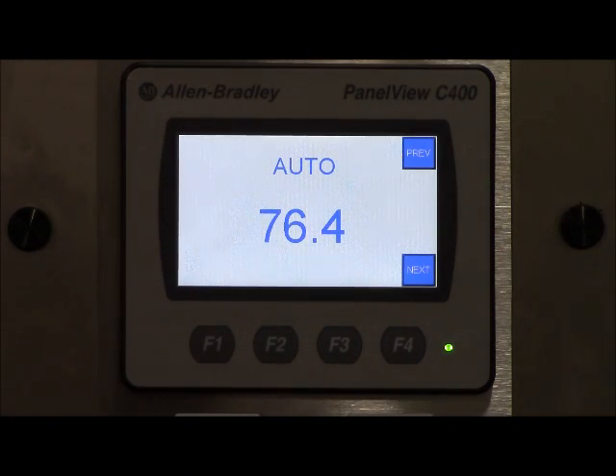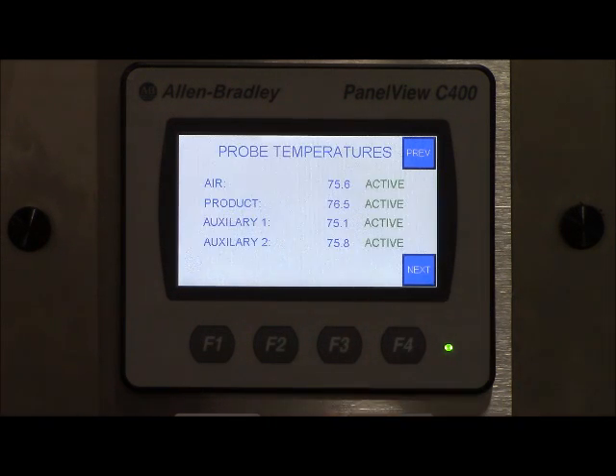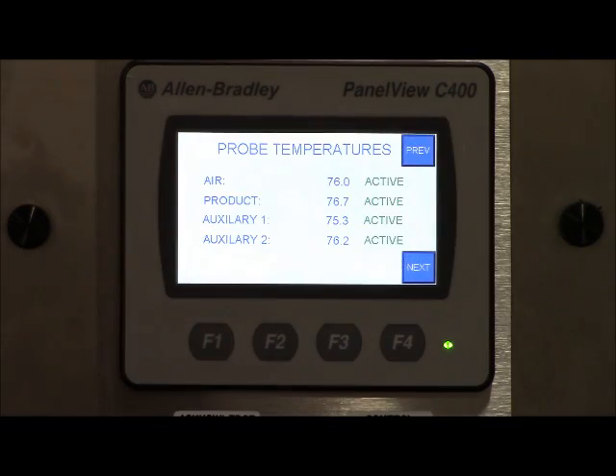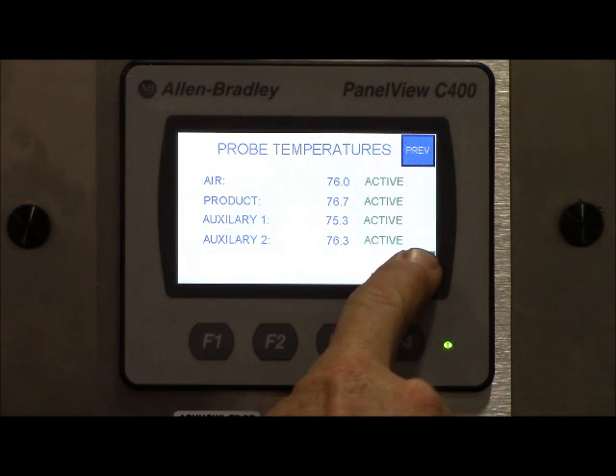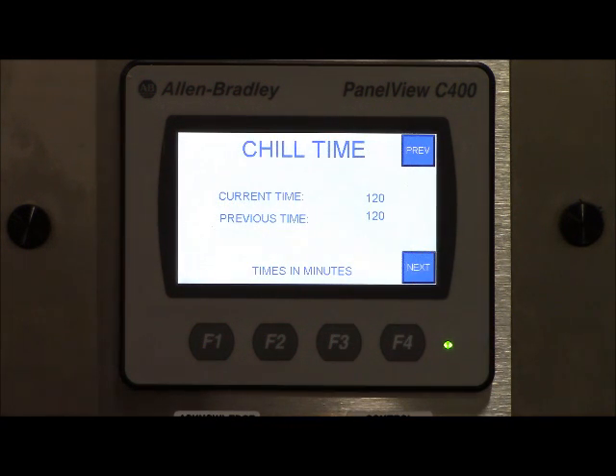The default controller screen will show you the product probe temperature, since it's the important one. It's large so you can see it at a distance. Push the next tab here, and you'll see all 4 temperature values. Push the next tab again, and you see the time since the temperature came down from 140 degrees. The number below shows how long the last chilling cycle took. The chilling time is defined as the time between 140 and 40 degrees, when the food is in the danger zone.